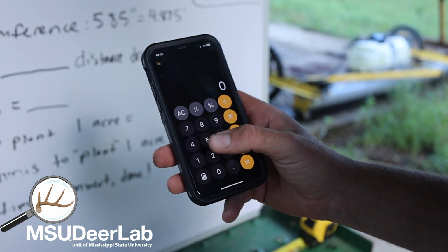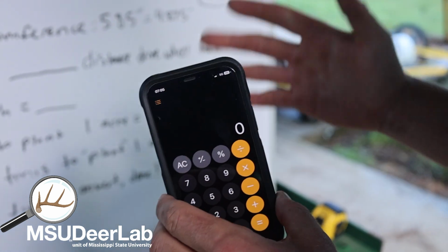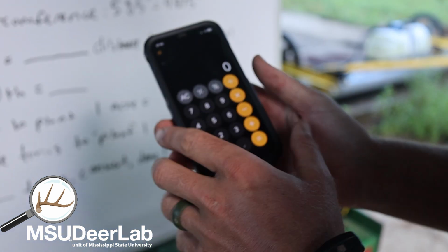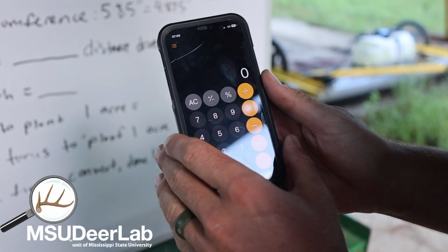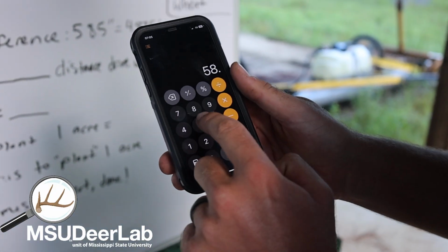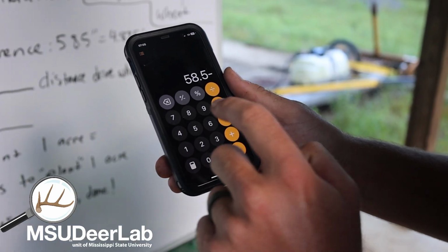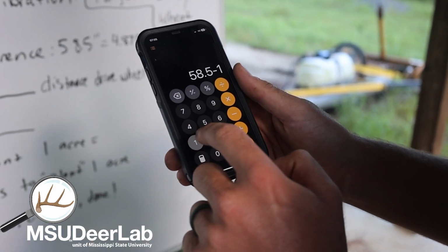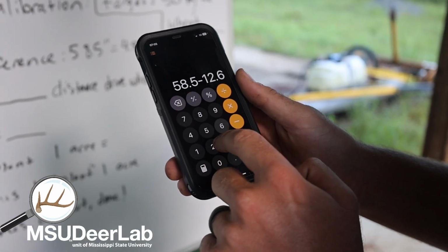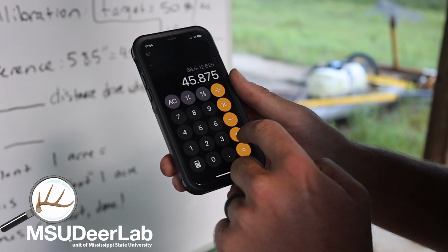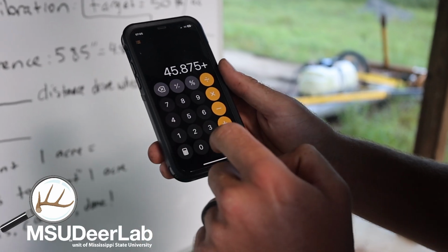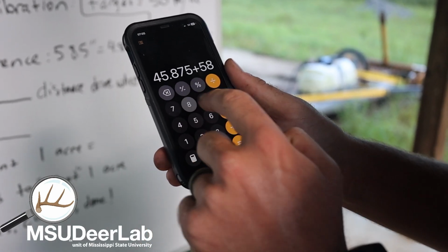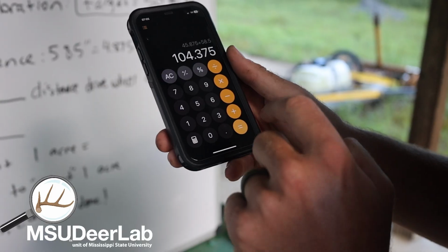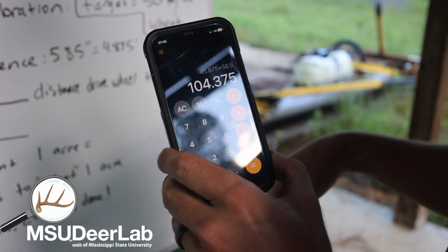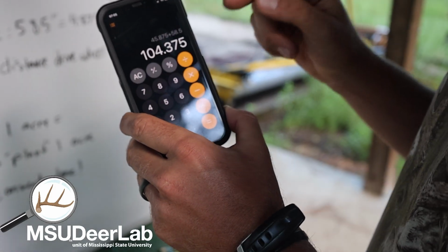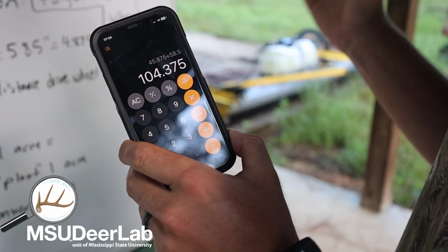All right, so now I've got to convert the measurements I just took to distance of drive wheel travel. So I'm going to take my original drive wheel circumference, which is 58.5 inches, and I'll subtract the measurement I just took, which was 12 5/8, which is 12.625. And I'm going to add that back to the full rotation we got out of the drive wheel, which is 58.5. So 1 crank of the calibration handle results in 104 inches of drive wheel travel.